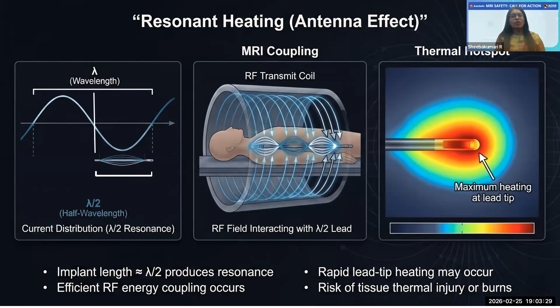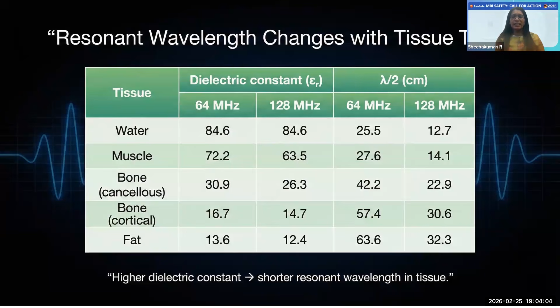For example, in muscle, the resonant wavelength for the RF pulse at 1.5 Tesla is 27.6 centimeter, and at 3 Tesla it is 14 centimeter. So a 27 centimeter implant will be safer to scan at 3 Tesla than at 1.5 Tesla.